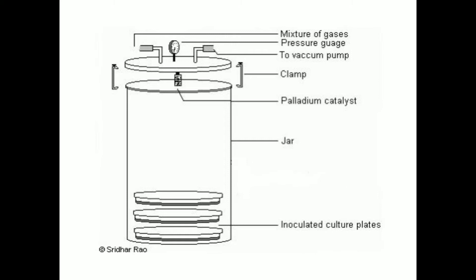The lid also contains two terminals that can be connected to an electric supply. There is a capsule containing alumina pellets coated with palladium, which is suspended under the lid by stout wires that are connected to the terminals to heat the catalyst for its activity. Nowadays this catalyst is also available active at room temperature.